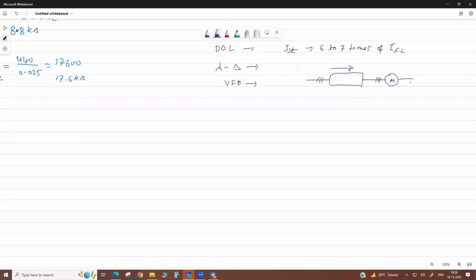So this VFD is not suitable if there is a full load always. It is a constant load. If there is a constant load on motor, always running on a full load, means rated load suppose. Then what is the load? Generally, if you use a blower or fan, pump, with constant flow, then this VFD is not advisable at all. When flow control is required, variable flow, then we can control the flow rate. Q is the flow. It is directly proportional to speed. If we reduce the speed with VFD, then we reduce the flow.